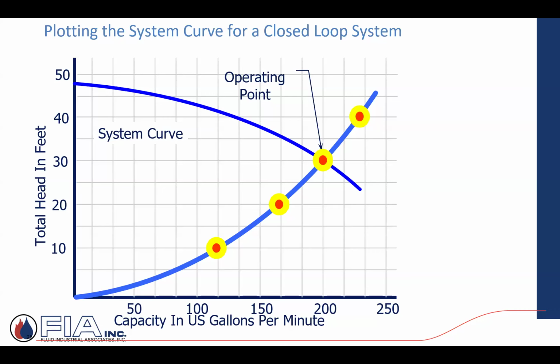Sure. Impeller trimming. The question coming from the class here was: sometimes maybe your design selection and then what happens out in the field isn't accurate. One of the solutions might be to trim the impeller, make it smaller, more in line with what actually is happening in the system. And yes, that does happen. Variable speed drives kind of take care of that as well. Instead of running at full capacity, they might knock that hertz down from 60 to 50 to 44 or whatever the number is.